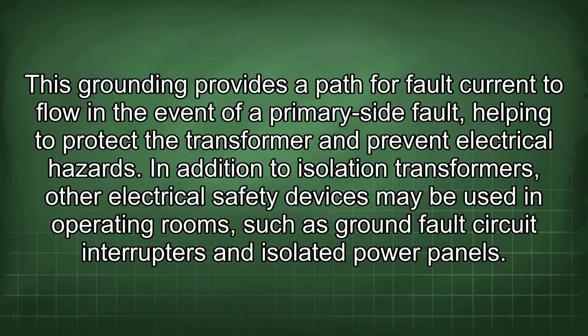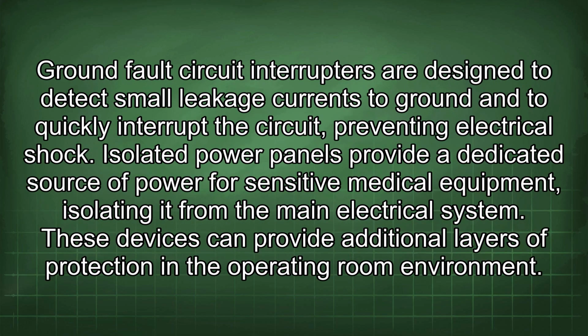In addition to isolation transformers, other electrical safety devices may be used in operating rooms, such as ground fault circuit interrupters and isolated power panels. Ground fault circuit interrupters are designed to detect small leakage currents to ground and to quickly interrupt the circuit, preventing an electrical shock. Isolated power panels provide a dedicated source of power for sensitive medical equipment, isolating it from the main electrical system.